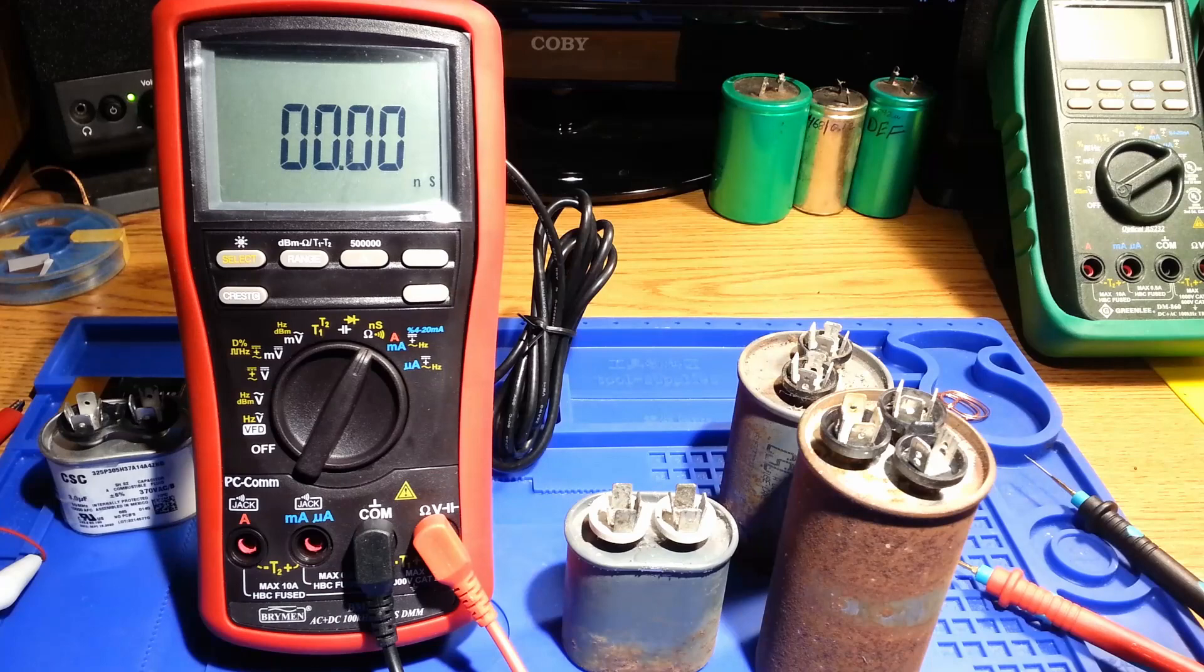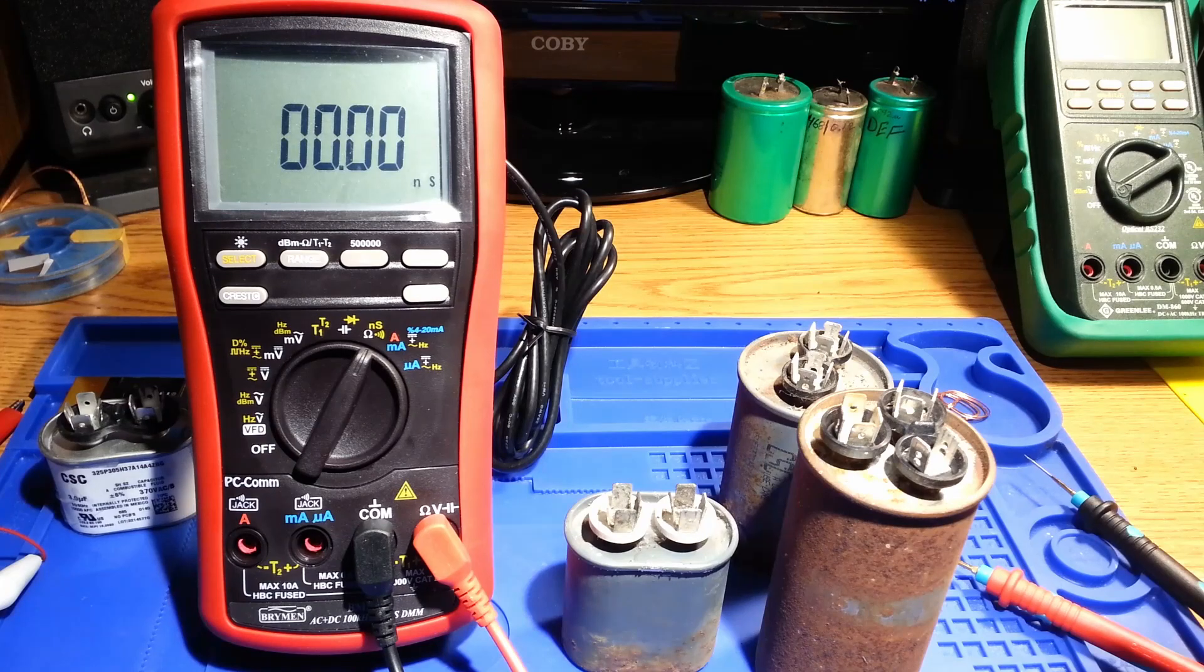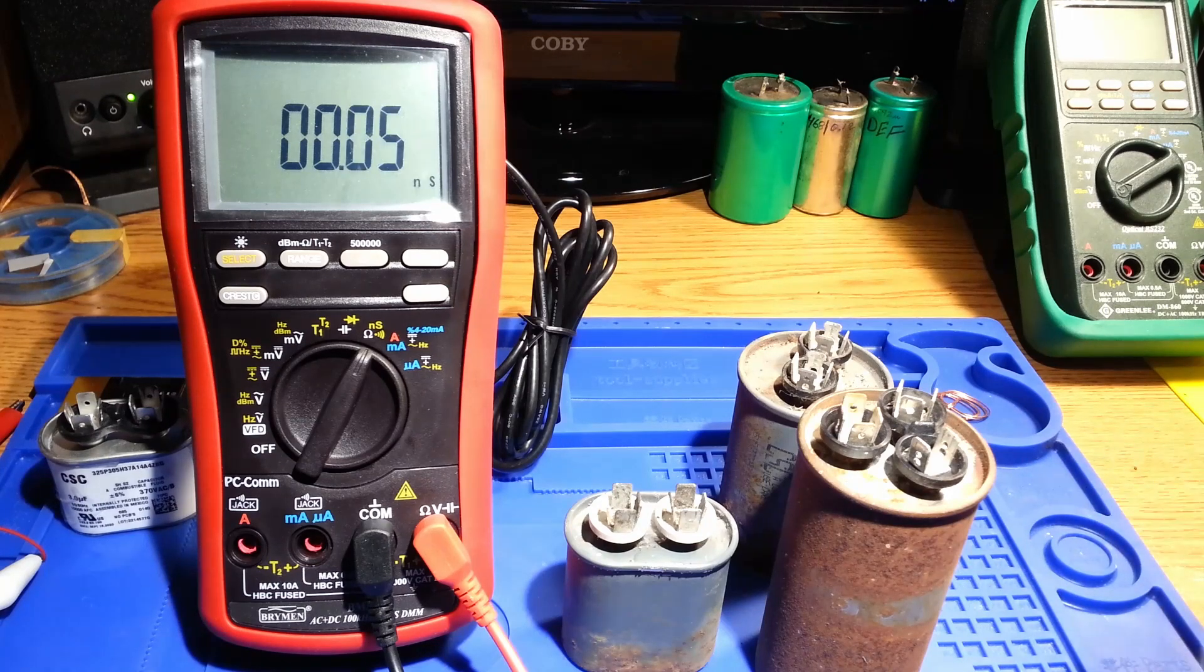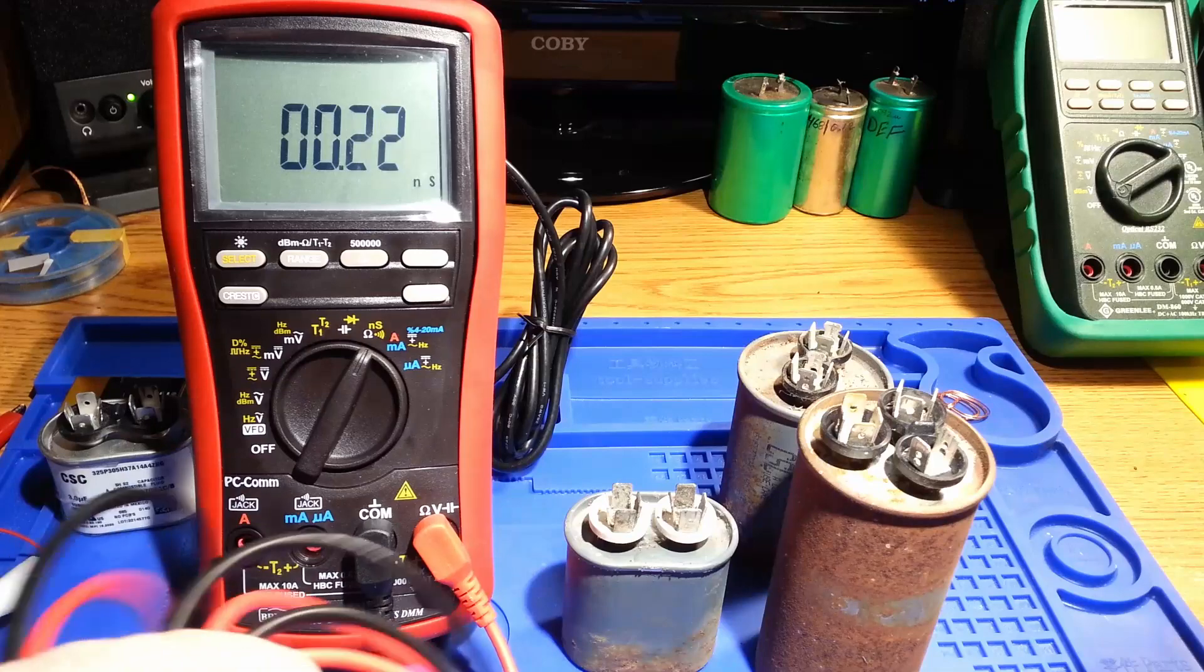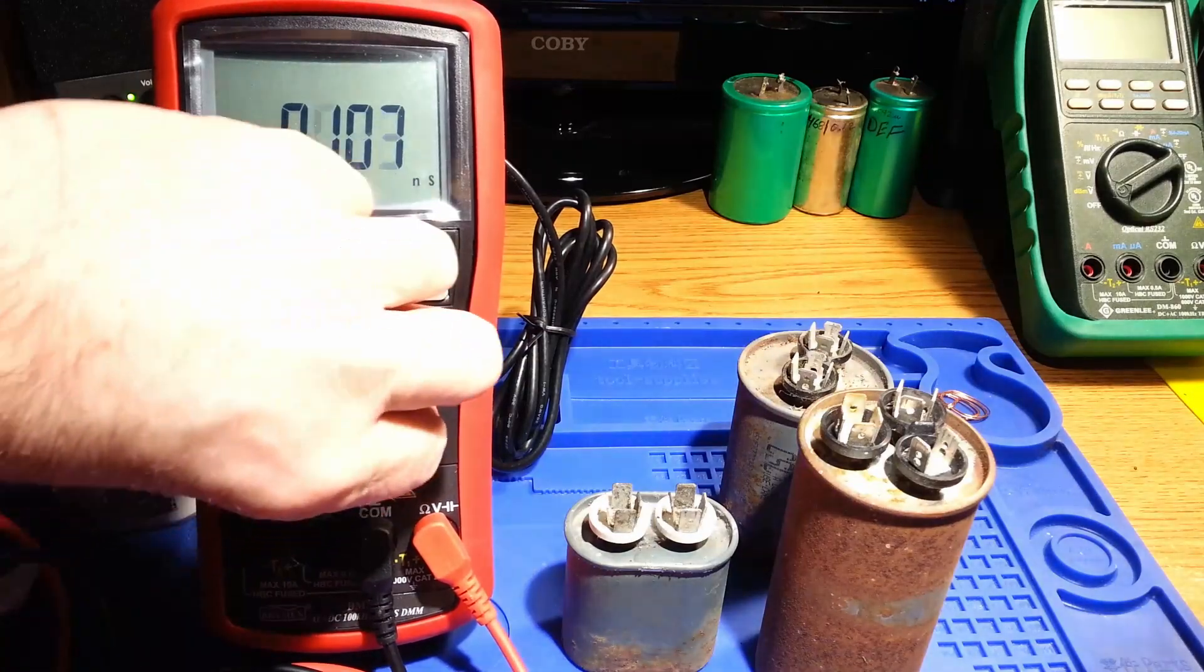Also, I ended up changing the contactors on my two units. They were as old as the capacitors, and over time they showed some wear and tear on them. I'm sure between regular functioning and voltage surges and the like, it probably was not a good thing for them to be left in place and expect everything to stay in service.